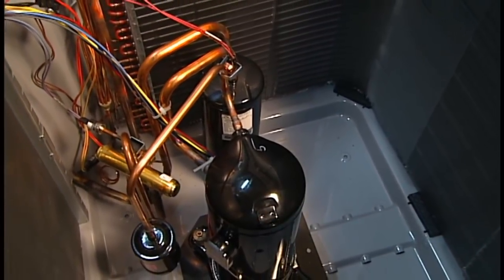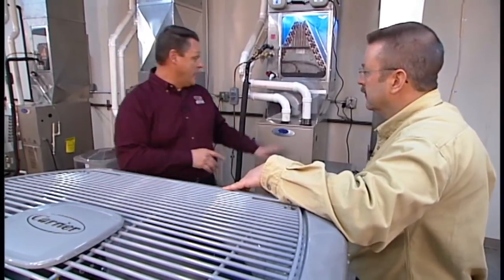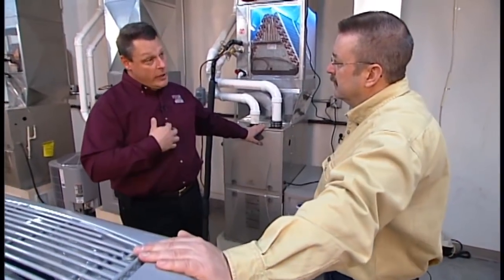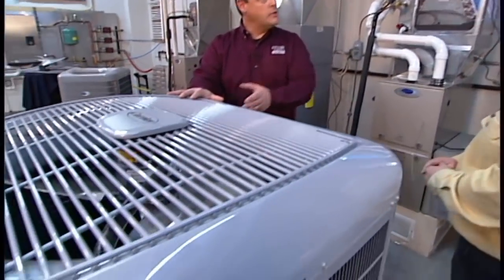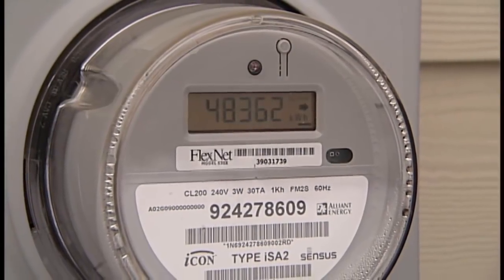So in our climate with a heat pump system, do we still need a secondary heat source? Ideally we do. There are limitations to heat pump system designs — we will not be able to get enough heat comfortably into the home as we get down to 15 and 20 below outside. Normally we would have a backup, and that's where the gas furnace comes in, or you could have electric. We like to see the dual fuel setup, which gives us the opportunity to use gas or electric for the heat pump side depending on costs, which vary regularly.